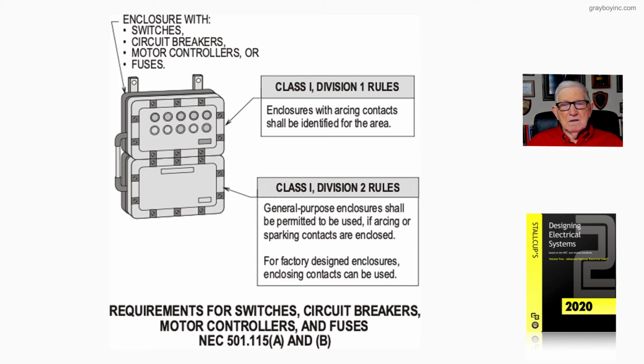So this is just kind of identifying enclosures. Now, enclosures for explosion-proof are Type 7, 8, 9, and 10 enclosures, explained in detail in NEMA 250. That's standard. Other types of enclosures can be found in Table 110.28 in the NEC.